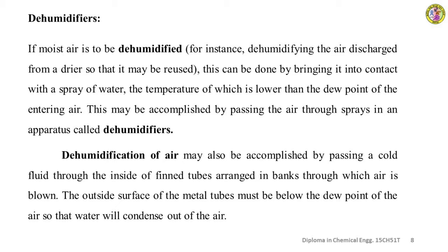If you have very moist air and it has to be reduced in its moisture content for use in an operation or to maintain a safer atmosphere around, then this can be achieved by bringing the moist air into contact with water, where the water temperature is below the dew point temperature of air, so that the air cools along with the water vapor, and the cooling of water vapor results in condensation of a part of moisture, thereby reducing the content of water vapor in the given air to maintain or to give dry condition to air.